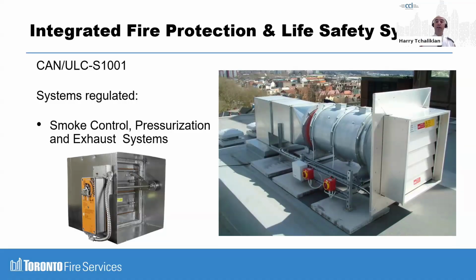Here's one that you may not be doing 100% of: your smoke control, pressurization, and exhaust systems. Part 7 of the fire code already required that you test your smoke control system in your building, if you have one, relative to the degree that you have smoke control. Not every building needs extensive smoke control, but you may even just have small pressurization fans for your lower grade stories, for example. Whatever your test procedures were for your smoke control system, for that once-every-5-year test, you have to make sure that every last component was in fact tested, not just your regular testing that your engineer designed for you. So it's just a higher level of testing for your smoke control.